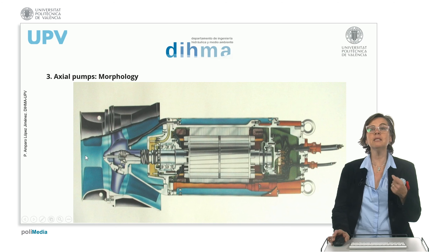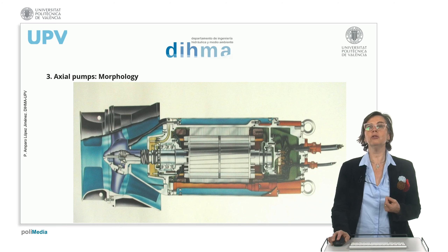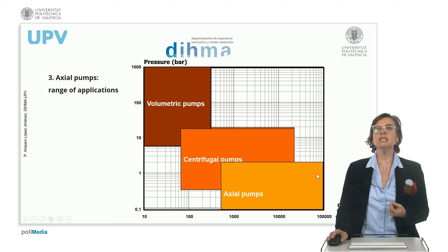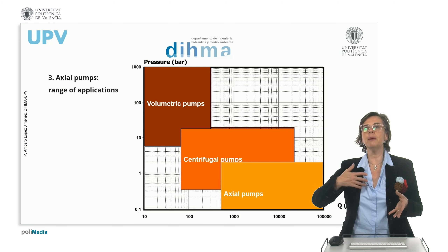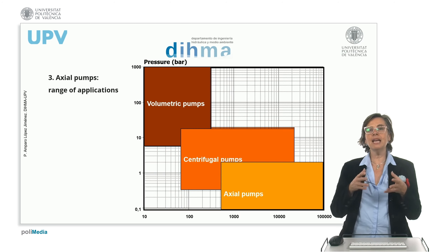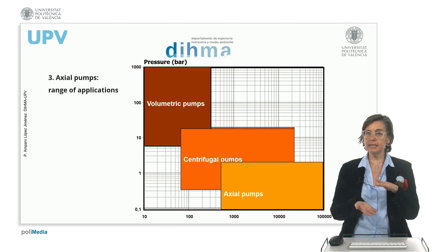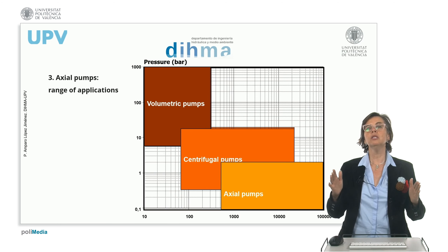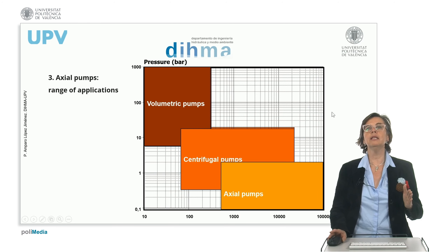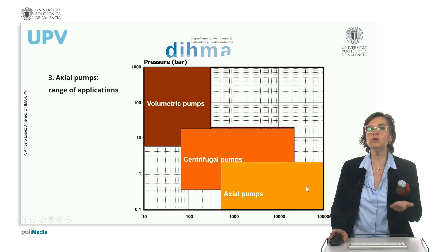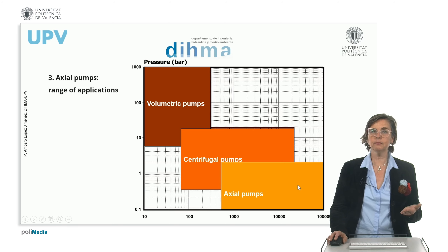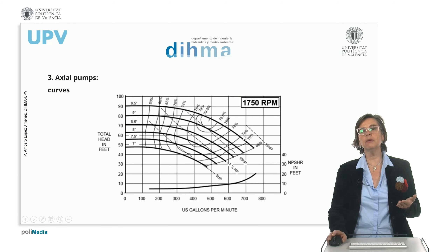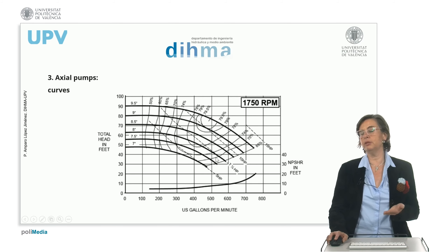The impeller is in the middle, giving impulse to the system. These machines are used in general to handle large flows because they have a high capability to move fluid, though they do not achieve very high heads. So in terms of flow versus pressure, they operate at low pressure and high flow. They are used in a wide range of applications with clean and dirty waters or other fluids. This describes the general shape of the characteristic curve for this type of machine.